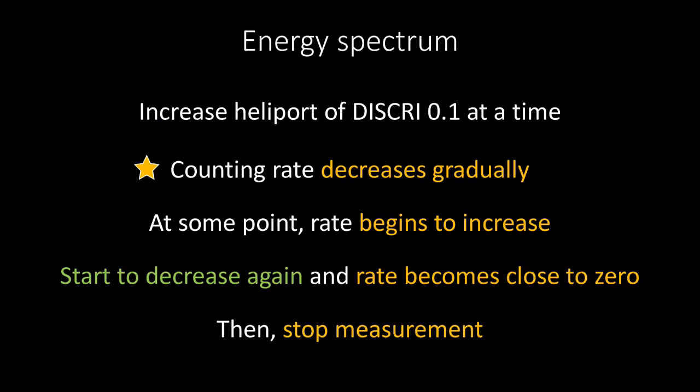At first, the counting rate will decrease gradually, but at some point, it will start to increase. If you continue, the counting rate will start decreasing again, and finally it will become almost 0. End the measurement there.